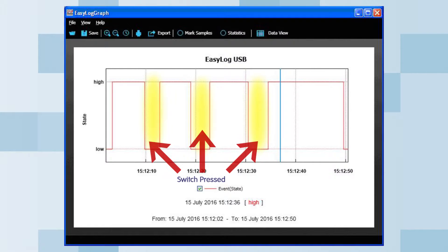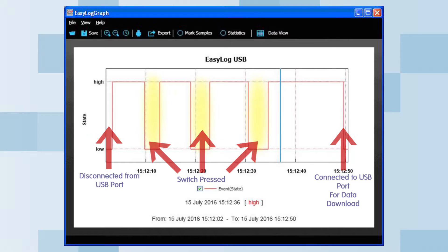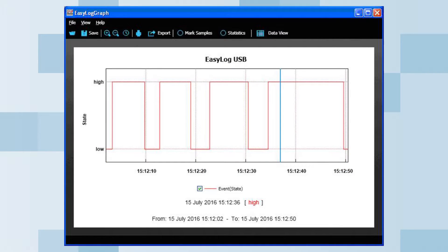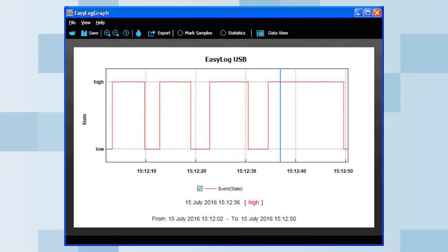In this graph, you have the state mode. In this example, there are three switch presses of a normally open switch with the logger set for falling edge type. Each switch press is approximately four seconds long. The recorded data shows you the date and time for each switch press and release. It is therefore possible to determine the time the switch was closed from the recorded data.